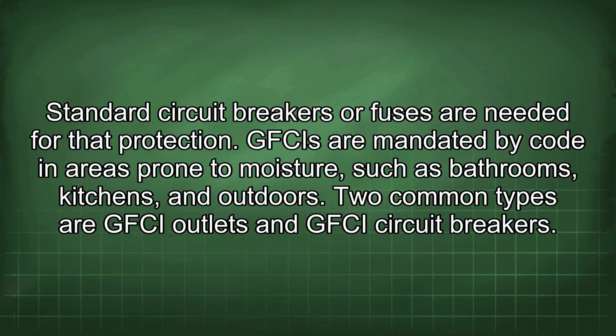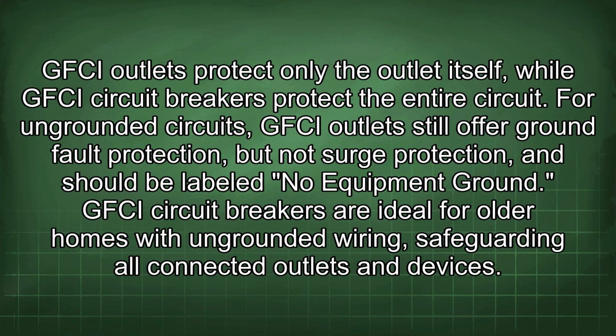Two common types are GFCI outlets and GFCI circuit breakers. GFCI outlets protect only the outlet itself, while GFCI circuit breakers protect the entire circuit. For ungrounded circuits, GFCI outlets still offer ground fault protection, but not surge protection, and should be labeled "no equipment ground." GFCI circuit breakers are ideal for older homes with ungrounded wiring, safeguarding all connected outlets and devices.